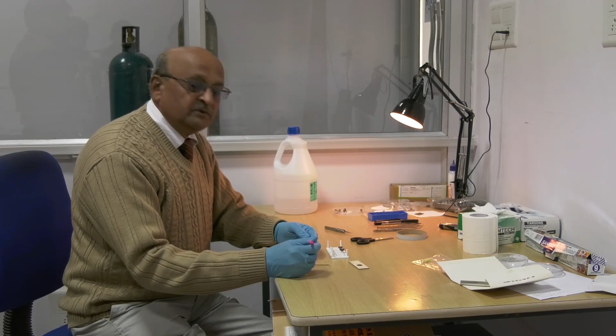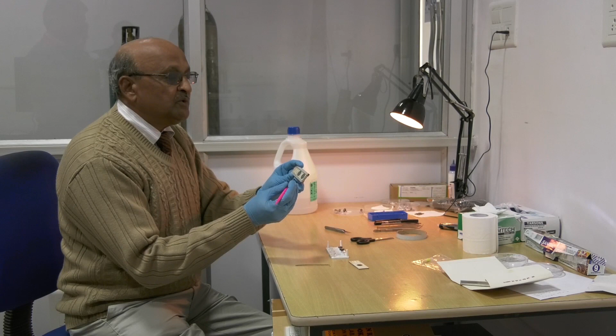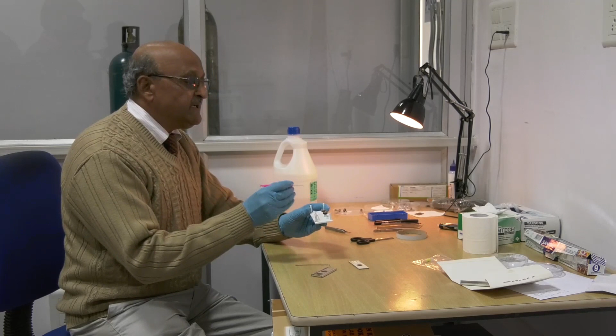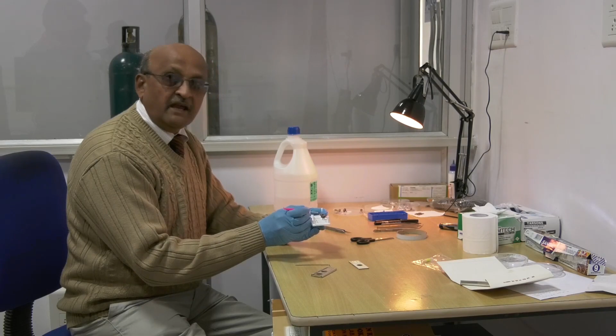Viewers, I want to demonstrate to you how the specimen is prepared for scanning. This is one of the corner slides used in micropaleontology, in which we keep the fossils in the two different slots. The specimen that we have to select for scanning is to be taken up with the help of a needle or a moist brush, and then it is placed on a metallic stub which has one adhesive piece of tape, and then this specimen is put on this tape, and it is ready for bombardment of electrons in the plating chamber. This machine is also an integral part of the scanning electron microscope, and it is called sputter coater.